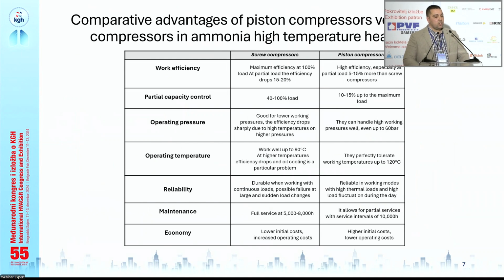Here, these are just some comparative advantages of the piston compressors toward the standard screw compressors. I will not go more in details. You will have everything on the slides. Basically, what we realized is that the work efficiency is better with the piston compressors and partial control of the capacity, because we know that screw compressors are mostly effective from over 40% of load, and for piston compressors we can go between 10 and 15% of load up to the maximum load.